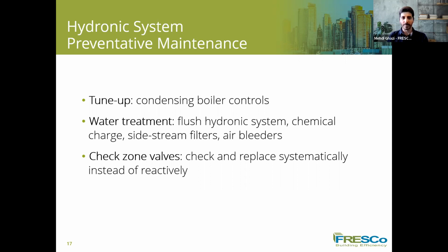and working properly. Water treatment, I mentioned: flushing the hydronic system, and charging chemicals, which I will mention in the next slides, with examples of chemicals that we can use, as well as side stream filters and air bleeders. These are some options that we have to keep our water treated and in good condition. Zone valves, as I said again, it's a smart investment to replace them systematically and periodically, instead of just reactively waiting for them to stop working and then replacing them.